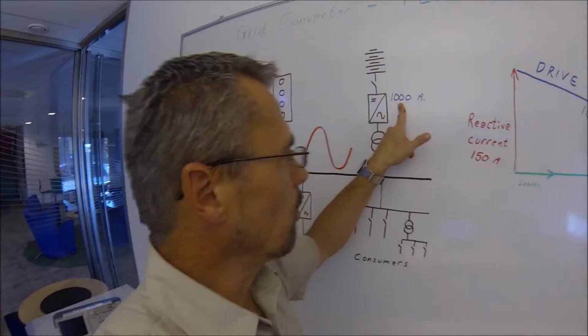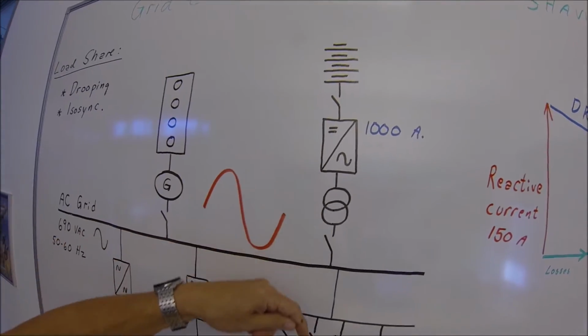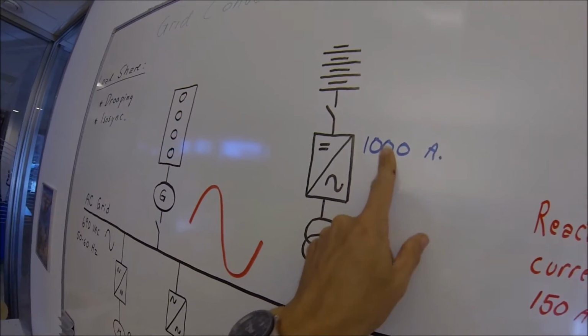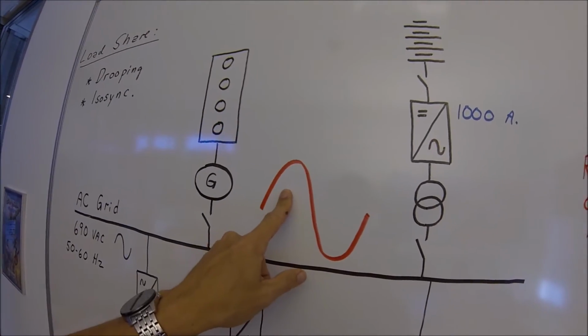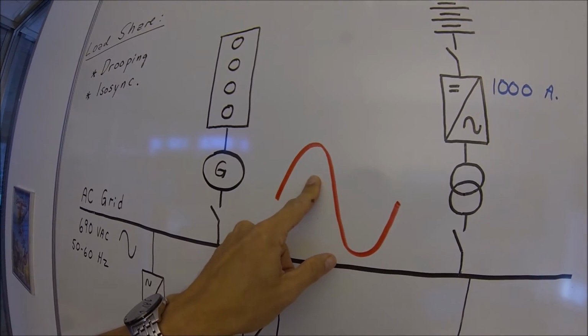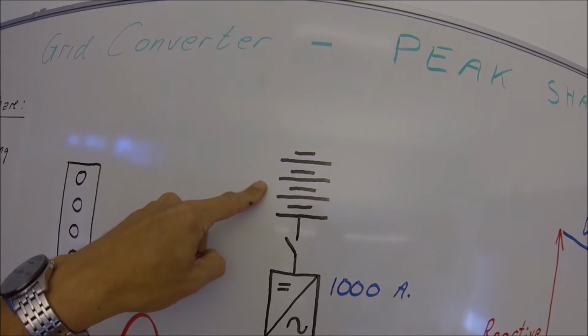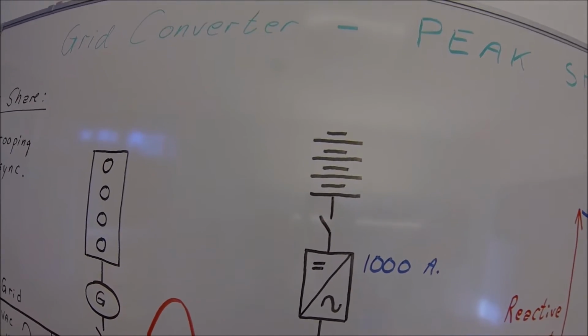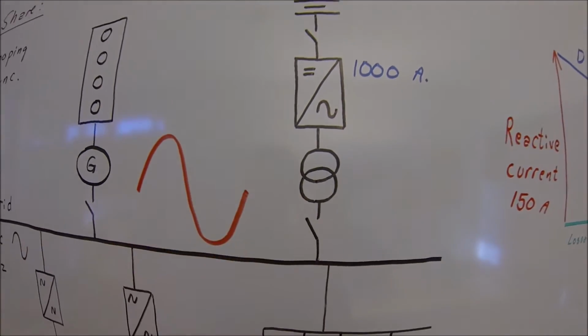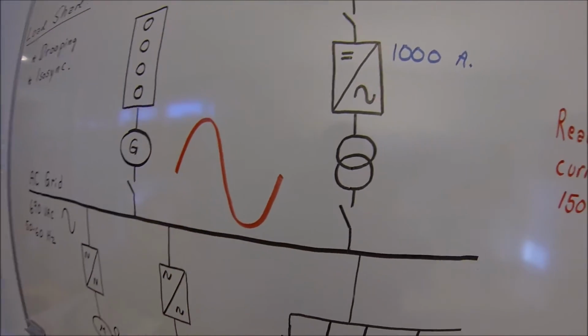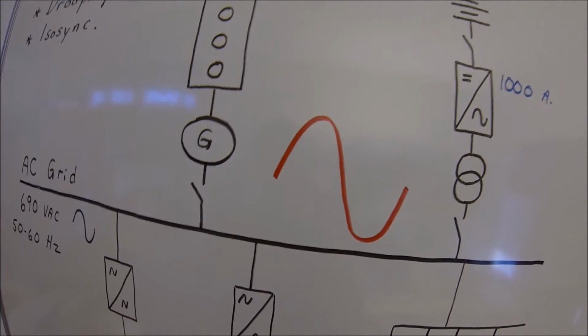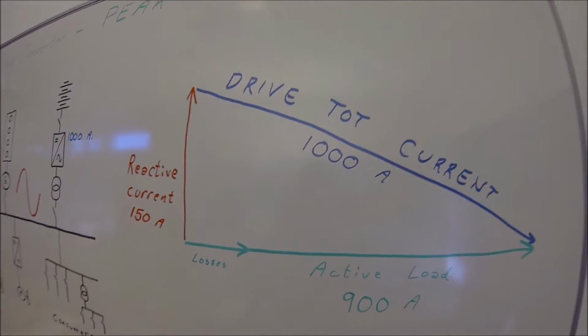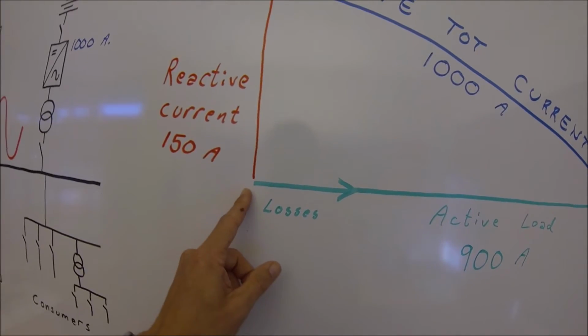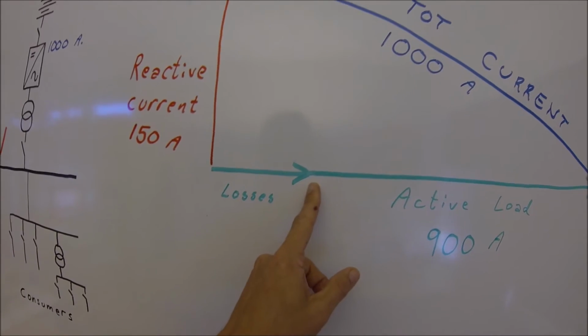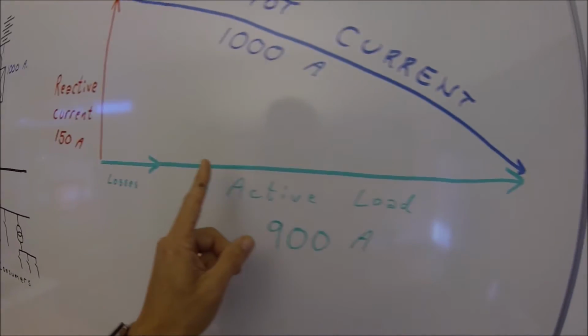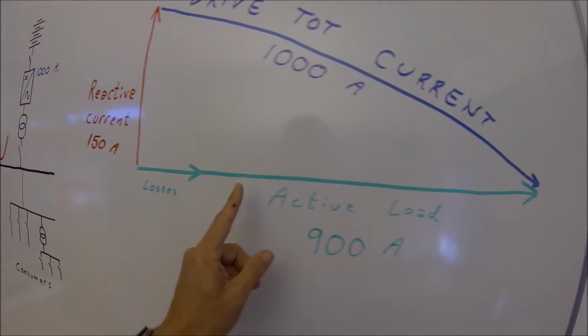When looking at the total ampere running through the energy storage, we have to be aware that the total current is the sum of active current and reactive current. The battery only sees active power because DC only works with active power. But on this side, we actually work with an AC system, which consists of both an active part and a reactive part. And this is how it looks in total. The losses over our filters and trafos, and then we have the physical job that we do for the grid and transfer to the battery.